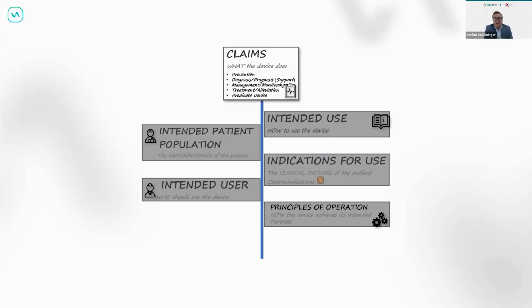So one thing I left on that slide is the overall and final outcome. That's the intended use. The intended use is normally a statement of 1 or 2, maybe 3 lines, which tells as precisely as possible and as broadly as possible what your product actually does. That can be: my product is utilized for diagnosis, or my product is utilized for therapy of a certain patient group, and therefore it is not intended for other things. That's a clear and simple description.